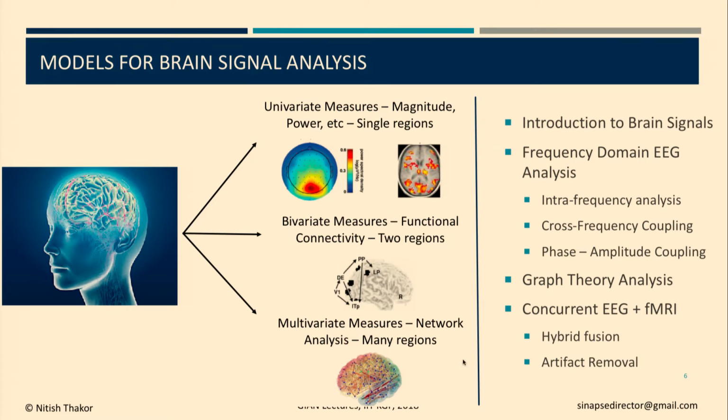So the picture on the left is an attempt at an MRI-like image of the skull or brain. A bright spot means there is a high electrical field. There are two approaches here. Mapping means that at every instant, the electrodes might be scattered, say 64 electrodes, symbolically on the head, because when you do EEG, you don't have a precise picture of the brain like you have with MRI. So you just pretend it's a circle and you know where all the electrodes are, and then you apply a color to any particular frequency, or to the power, or to the power and frequency. In some way you make an image out of it, because an image is a little easier to understand than those 64 channel waveforms.